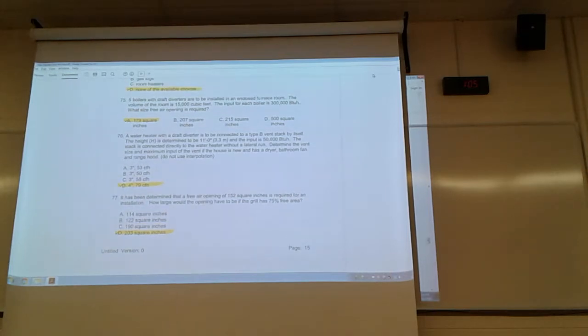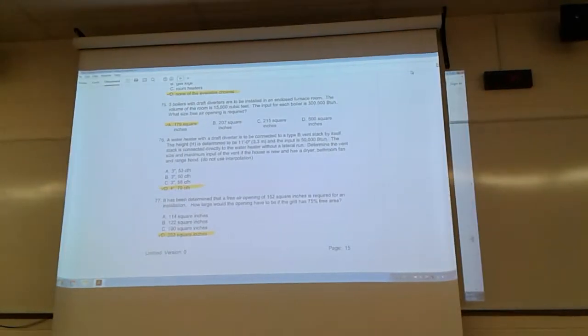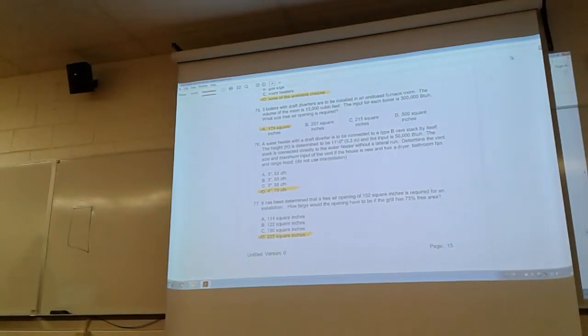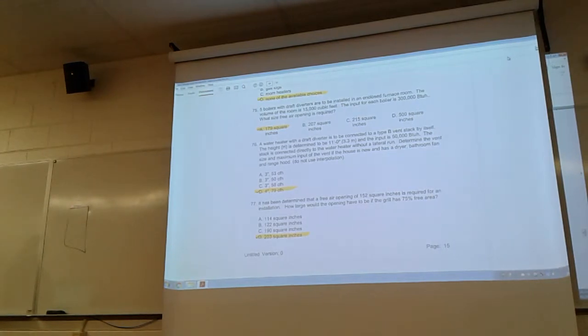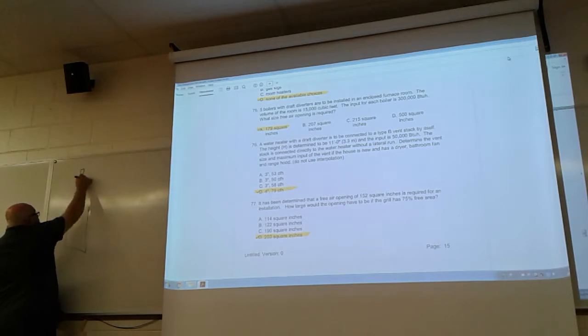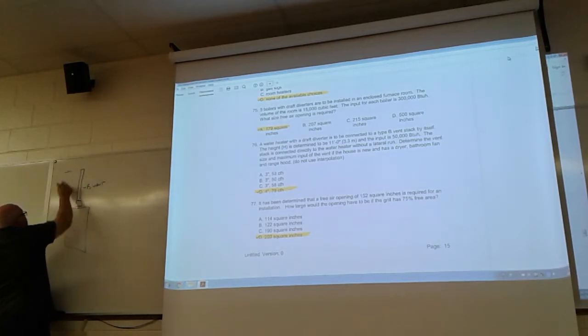A water heater with a draft diverter is to be connected to a type B vent. Now, I have my suspicions that this might be from an older code book. So we've got a water heater with a draft diverter, so let's draw a picture on our scrap piece of paper. It's connected to a type B vent stack by itself. The height is 11 feet, so we've got B vent, and it is 11 feet.